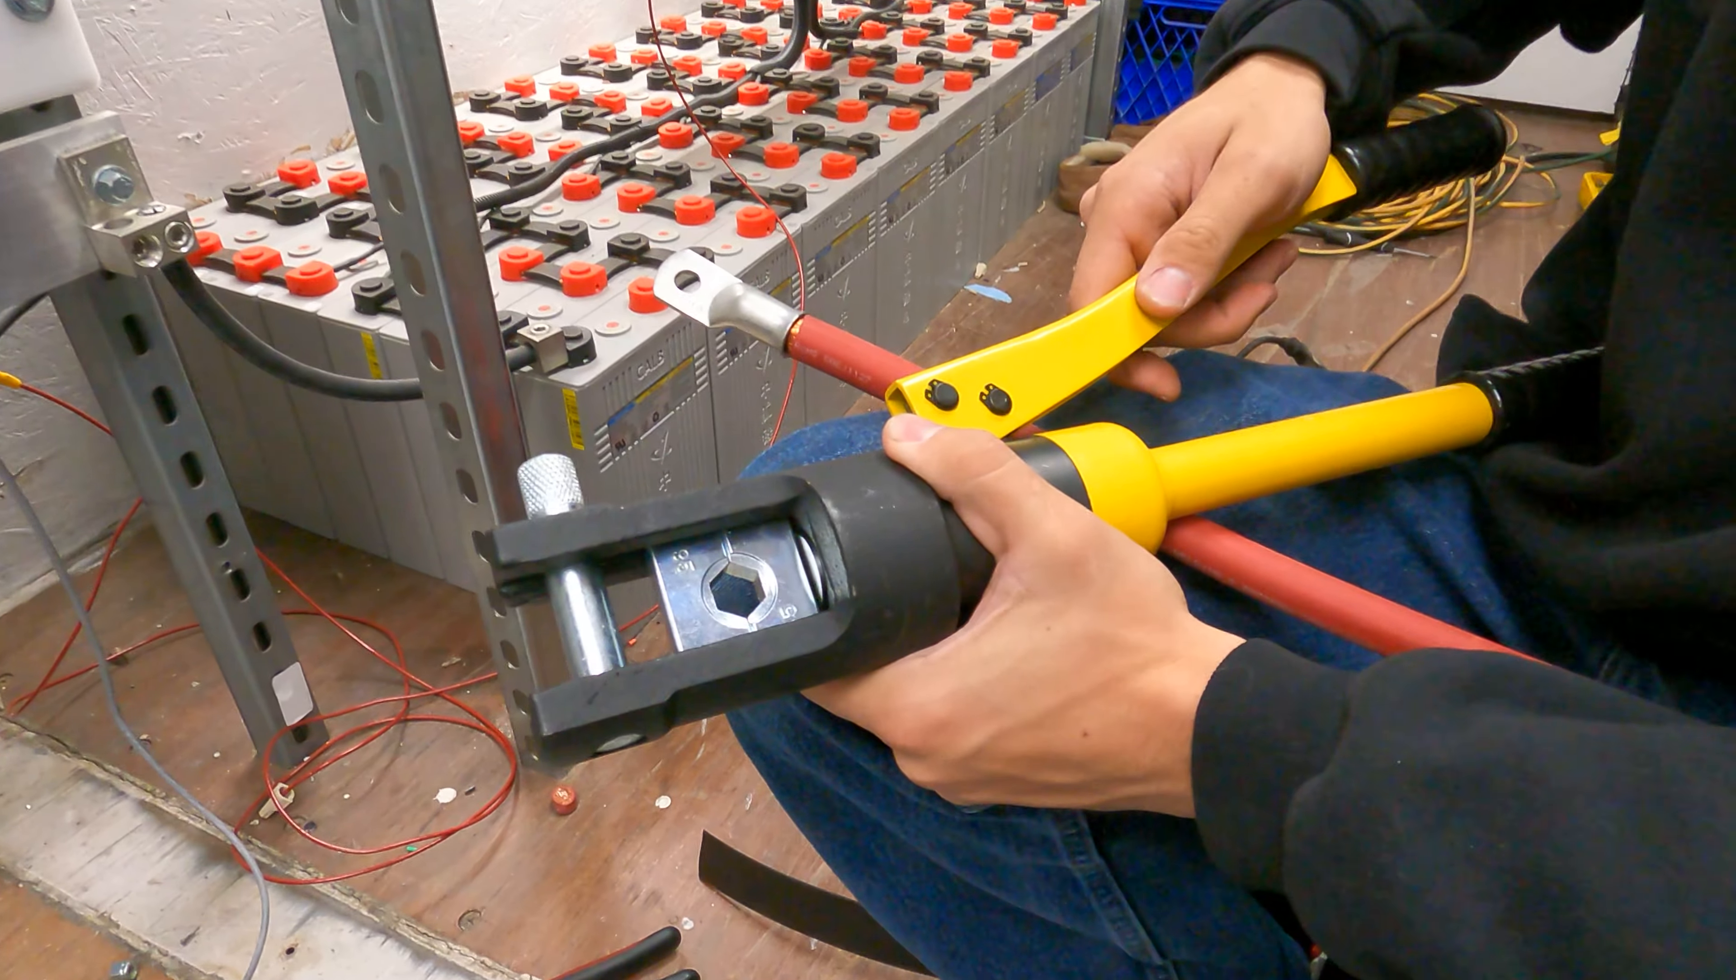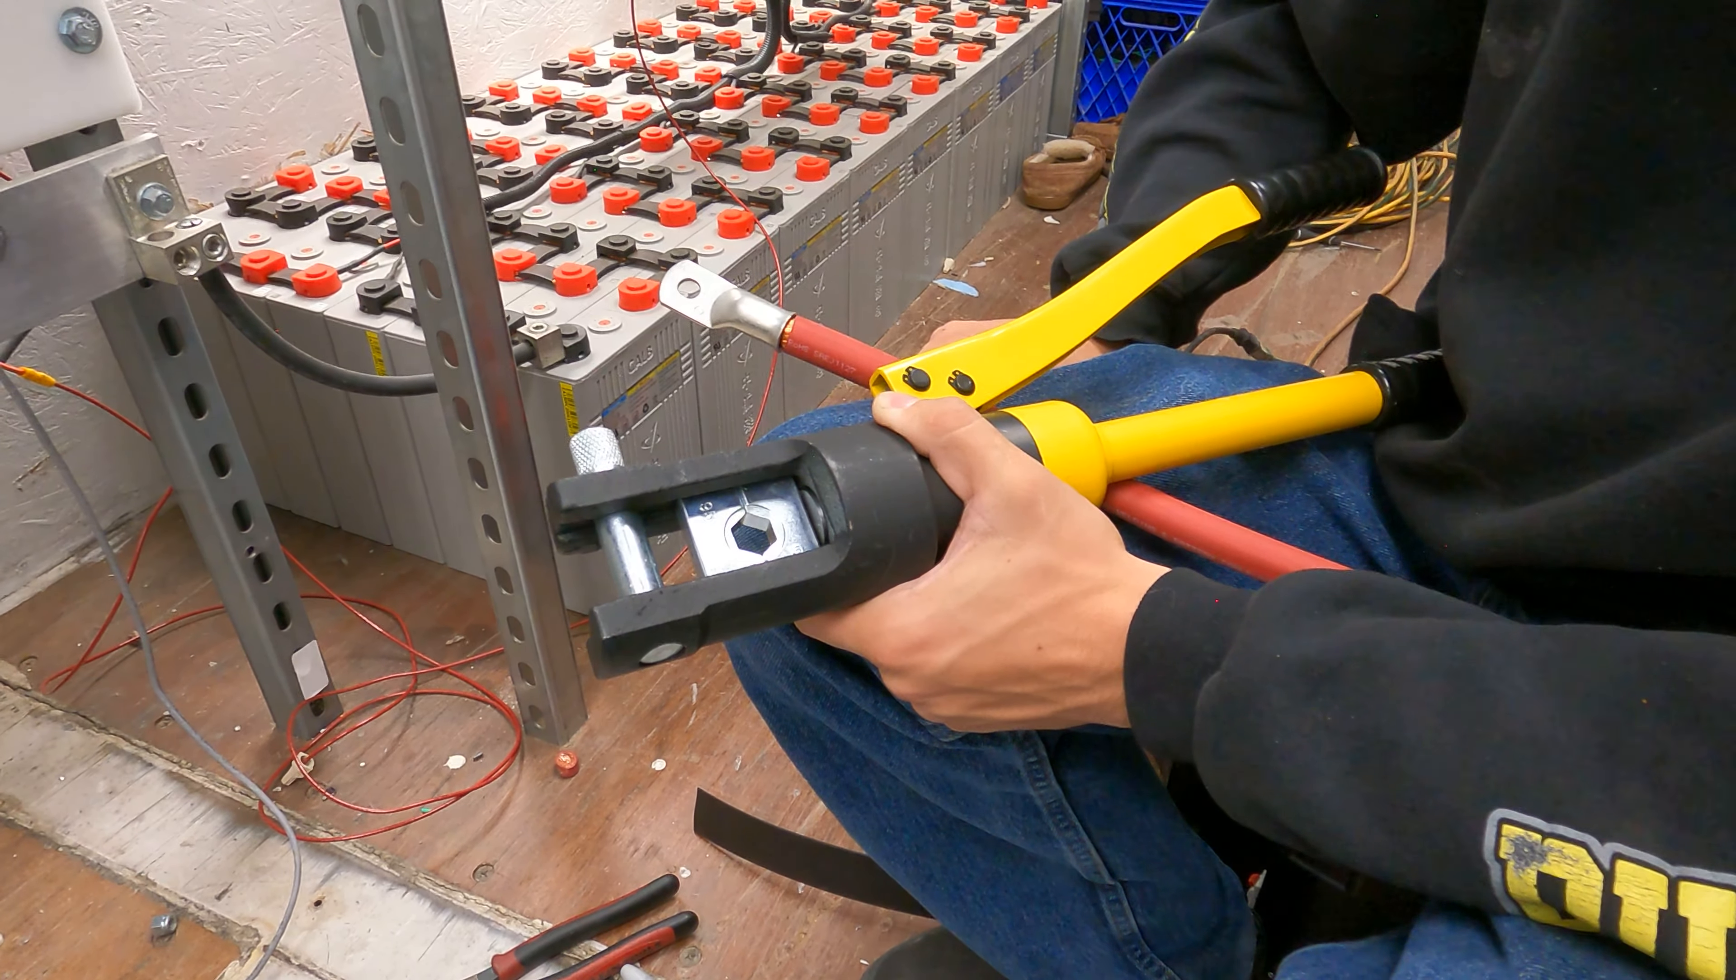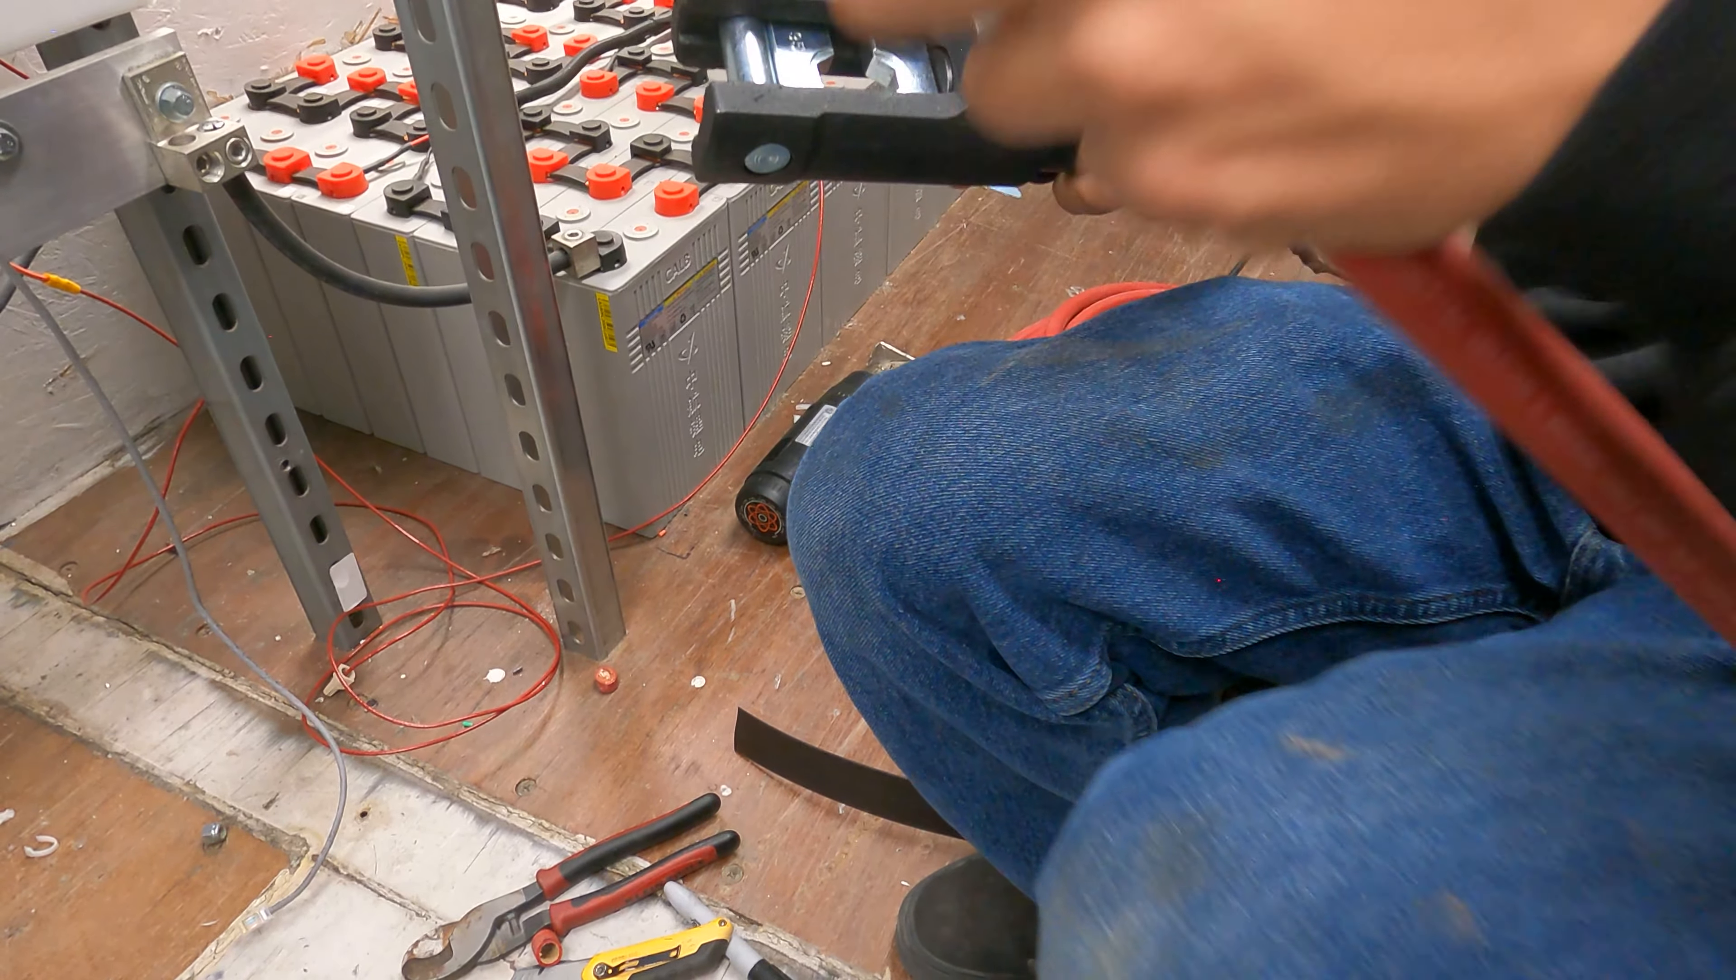Okay, so here on my hydraulic crimping tool, I have the correct die installed. In this case, it's stamp 95 for this 4-0 cable. This is in millimeters square, I believe, but there's a conversion chart and it crosses over to 4-0. So I'm going to spread these lugs out. And by the way, if your tool is not already, you're going to want to loosen it up by turning it to off and then close it back up so that now the dies are spread apart.